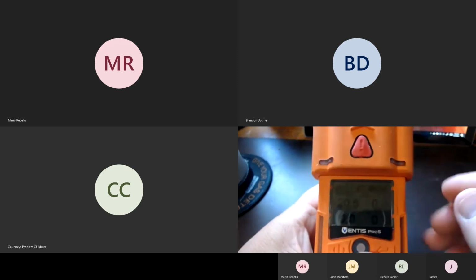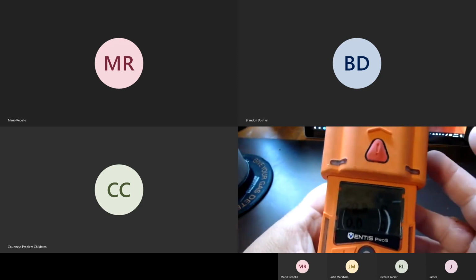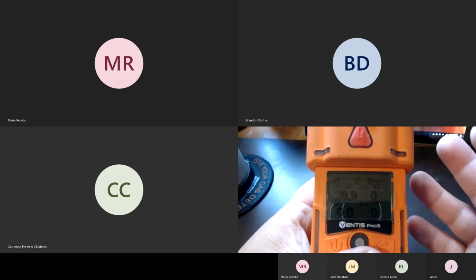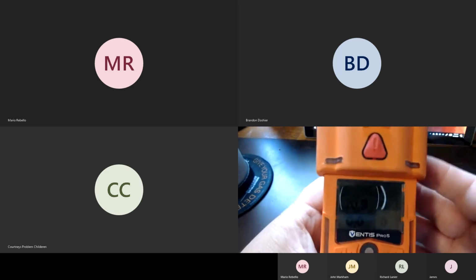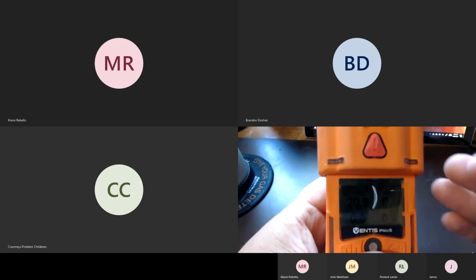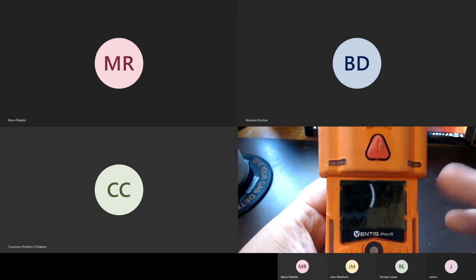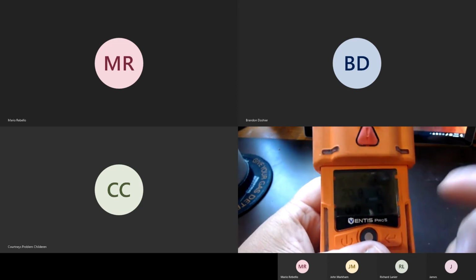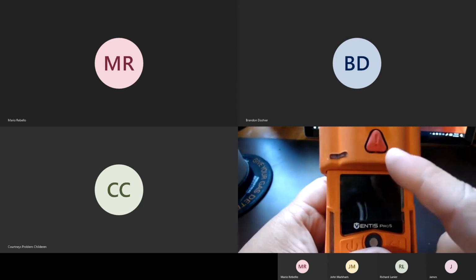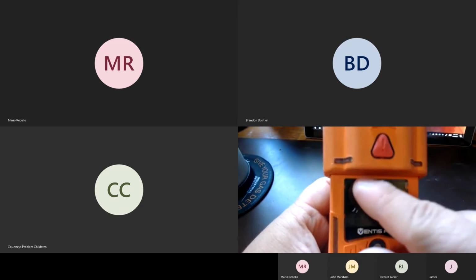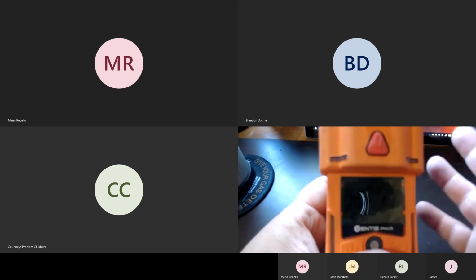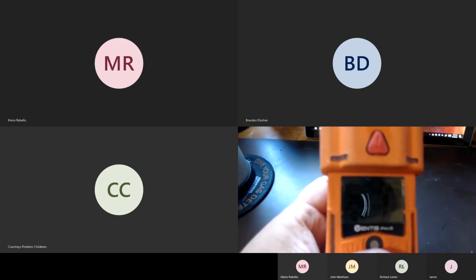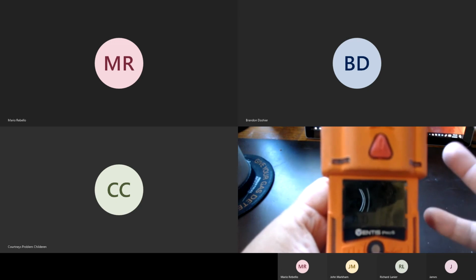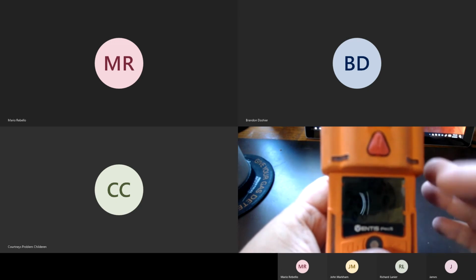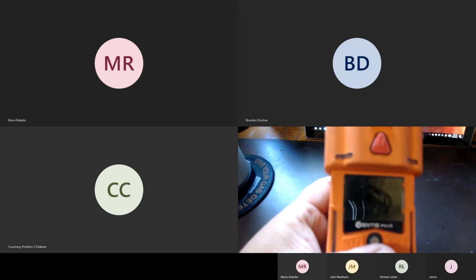So what that means is whenever you have a completely empty battery symbol, you still have about a quarter of your battery remaining. Whenever the battery is completely dead or it's starting to die, on the screen, it'll come up with a big battery symbol with a line through it. And then it's going to be beeping and flashing at you, letting you know, hey, I'm going to die. You know, you got about 20 minutes of runtime when that happens. And that's whenever you know, hey, we need to get that changed out.